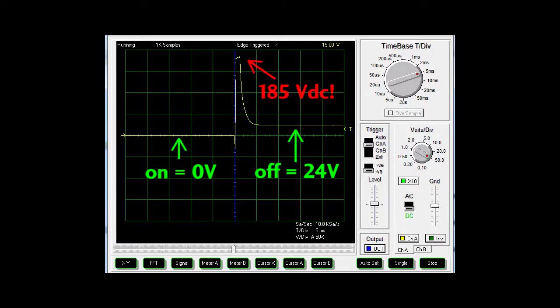My oscilloscope has its own surge protection built in and it's actually limiting the spike. The voltage really goes up here someplace, but you get the idea. It's hundreds of volts and when that huge voltage spike hits your PLC's I/O, it can cause an arc to jump the PLC's output relay contacts which will shorten their life and it can destroy a transistor output.